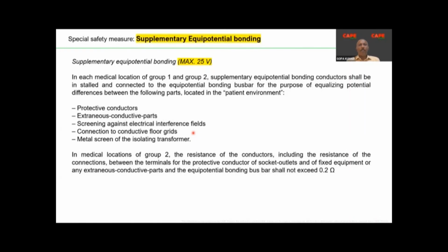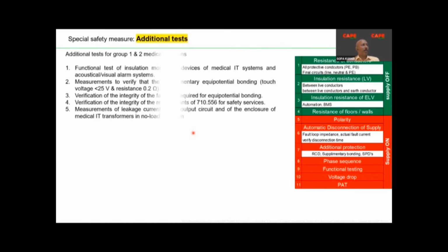Unfortunately, a lot of biomedical equipment vendors will ask for a separate earth pit. They say, my equipment is very special, I need a separate earth pit. If you connect your biomedical equipment to a separate earth pit, this mandatory requirement cannot be fulfilled, which is also one of the reasons for compromising safety in a medical location.